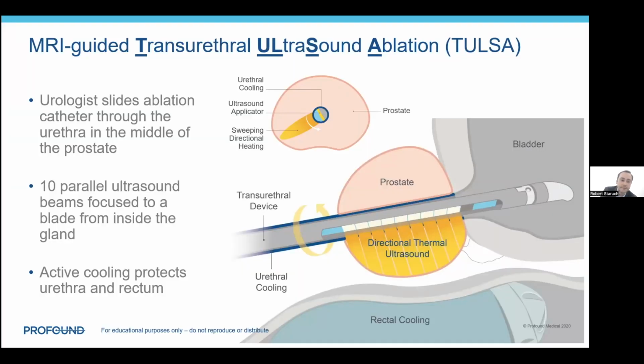So Tulsa stands for transurethral ultrasound ablation. It's transurethral because the urologist is able to slide the active part of the ultrasound applicator through the urethra to put the active part of the transducer within the prostatic urethra, and the tip extends into the bladder. Ultrasound, because it's using ultrasound similar to HIFU, but different in terms of using 10 parallel beams of sound, as opposed to focusing energy into one small point.